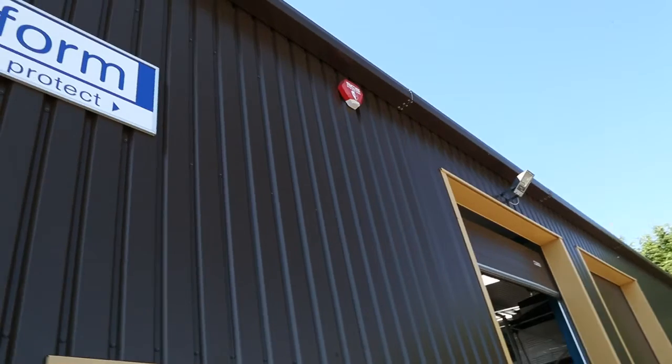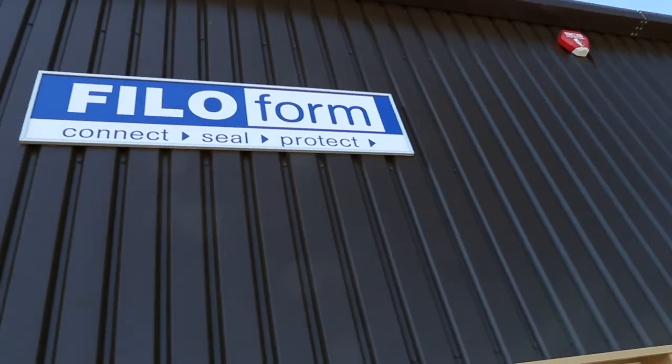FiloSeal Plus HD has been tested up to 2 bar pressure on its back face, 100kg pull force and cable flexing 10x45 degrees whilst holding 1 bar pressure.